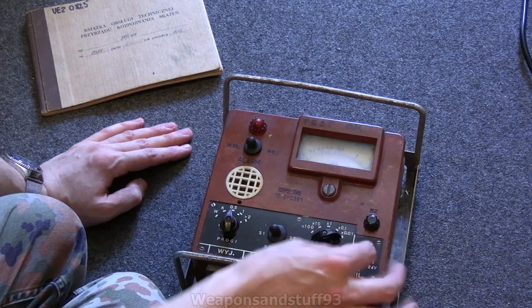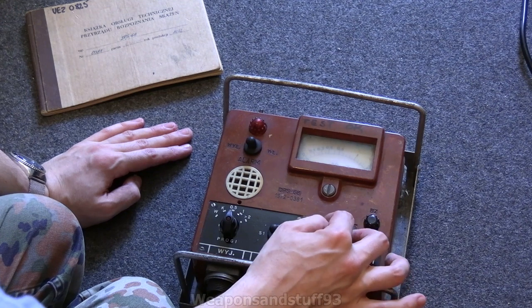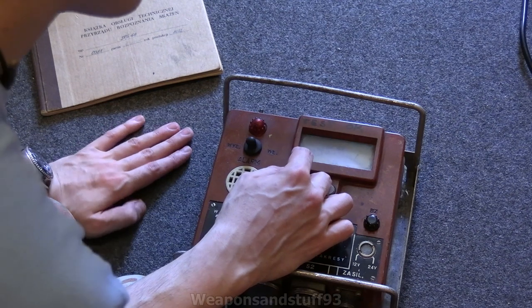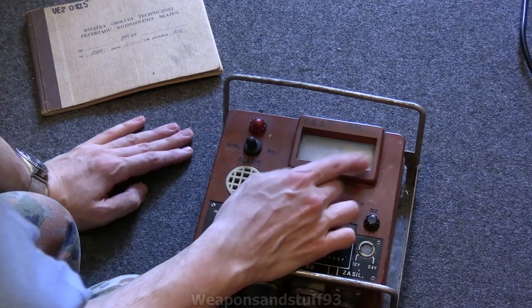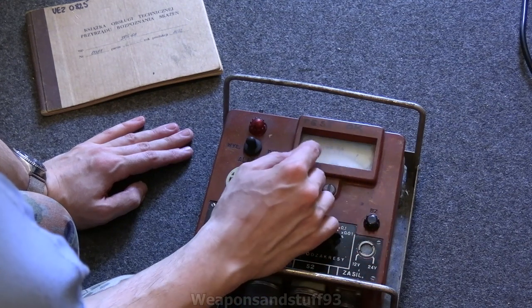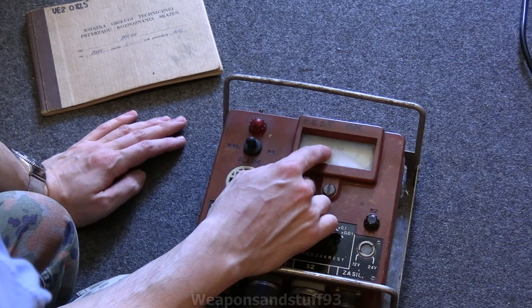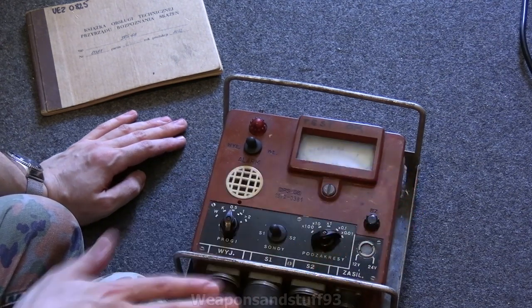This is the range switch. It does times 0.01, times 0.1, times 1, times 10, times 100. On the times-1 scale it does 0, 0.1, 0.2, 0.3, 0.5, 1 and 2 — that's roentgen per hour. So basically it does the 100 milliroentgen scale. It's a non-linear, sort of logarithmic scale, so the numbers go up faster.